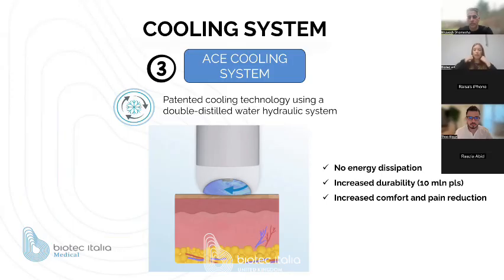frequency. So we need a cooling system in order to dissipate heat because we can overheat the transducer and we can decrease the durability of the transducer. And water is the natural medium that dissipates heat faster and better. So we have a cooling circulating system inside the handpiece that works with double distilled water. And the most important thing is that this water inside is not static like in traditional HIFU, but it is dynamic. This dynamic system allows us to dissipate the energy of the ultrasound better and faster, and increases the durability of the transducer.